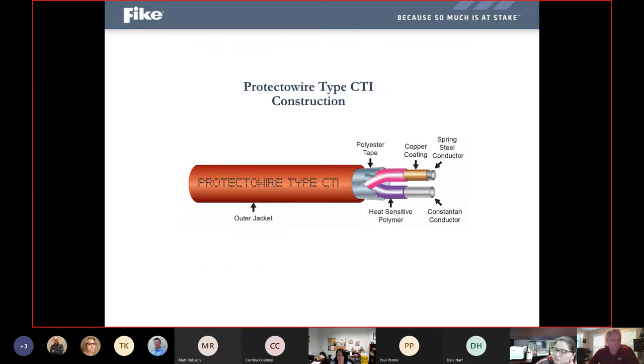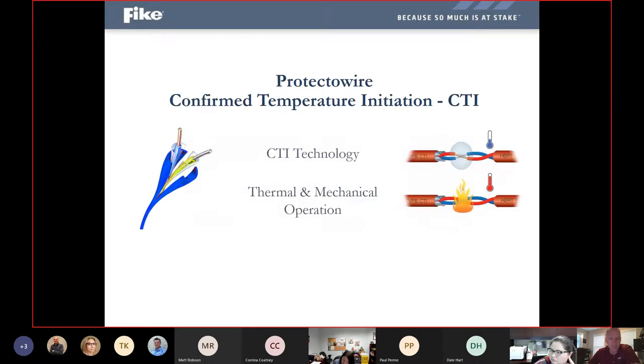And basically, all it is is a two-conductor wire with an outer jacket and two conductors on the inside that are coated with some additional polymers that are heat sensitive. And we've got a lot of different ranges of specific temperatures as to where this stuff starts to melt. And all that the system is looking for is a short circuit along the cable, meaning the polymers have melted off and now those two conductors are exposed and touching each other, basically closing the loop, closing the contacts to initiate or indicate we've had a detection.